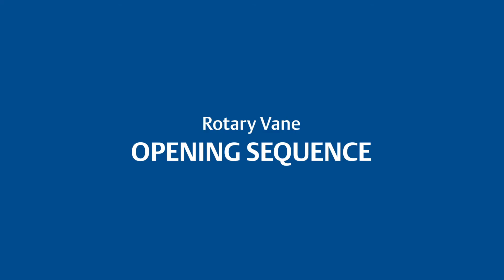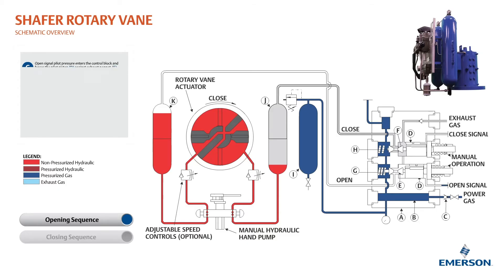This is the theory of operation for the opening stroke for the Shafer rotary vane actuator. Open signal pilot pressure enters the control block and forces the pilot piston against the exhaust poppet, forcing it onto its seat. The power poppet is then forced off of its seat.